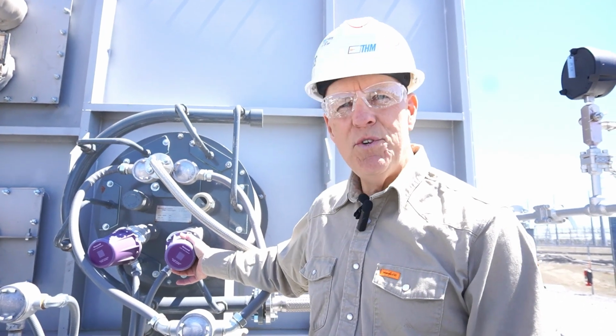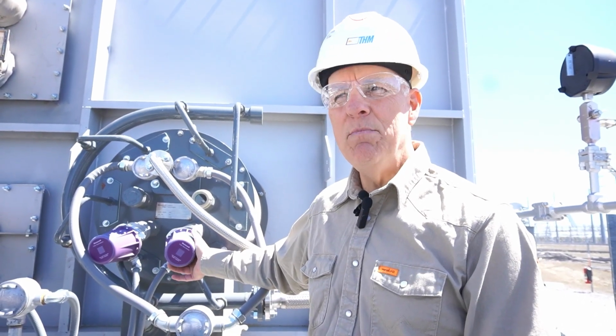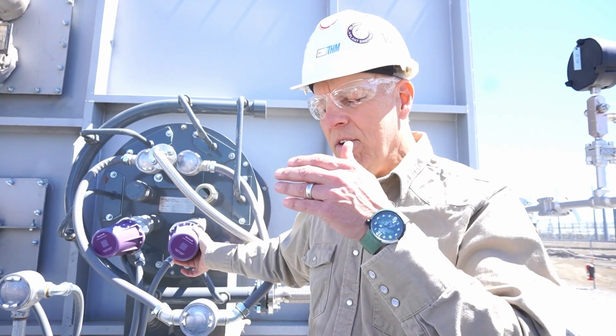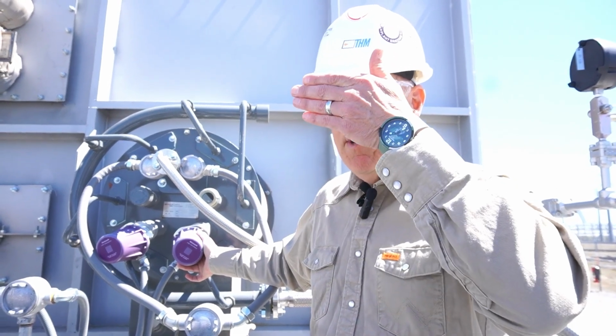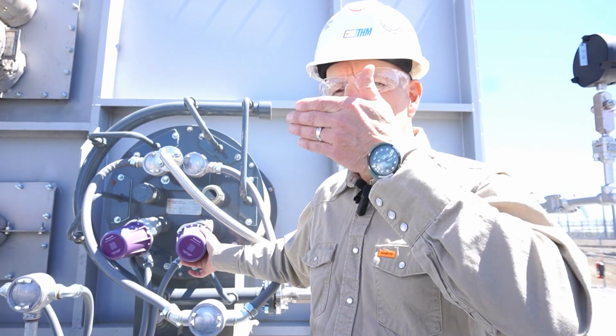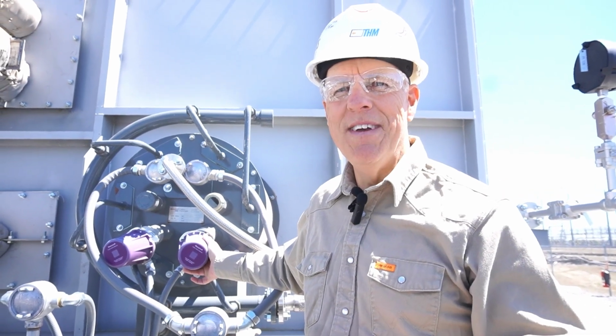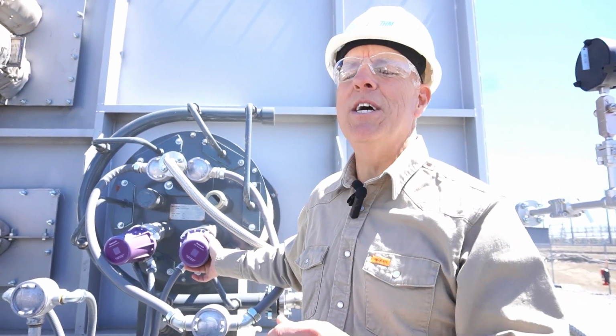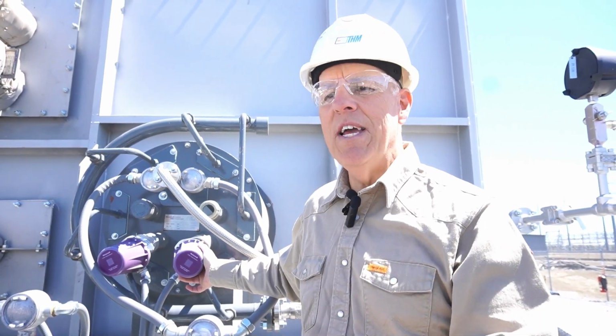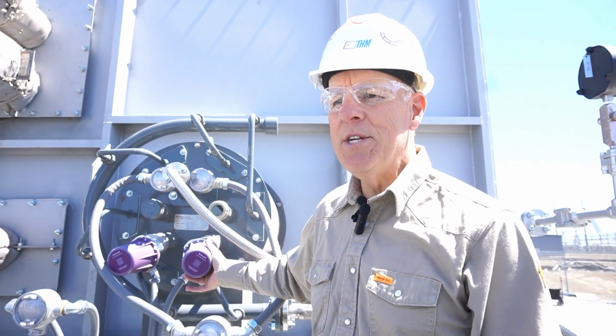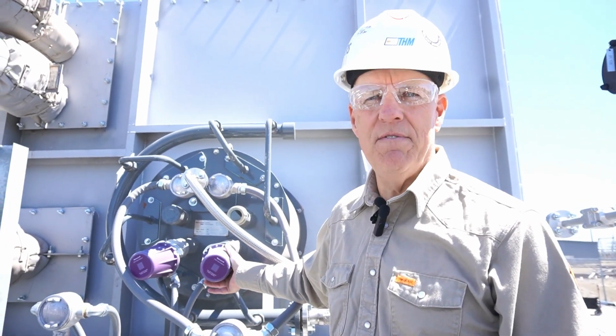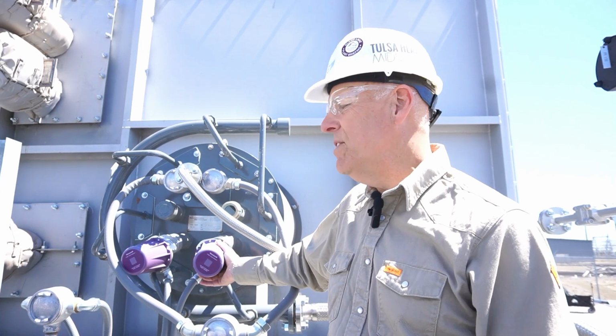They're also called self-checking scanners, meaning that they're looking for flame, but sometimes they cover up their eyes to make sure that, hey, when the eyes are covered, we don't see flame, right? So they make sure they're not tricking themselves. So it's self-checking, constantly looking for flame, constantly checking itself to make sure it doesn't get a false positive. False positive on flame is not good.